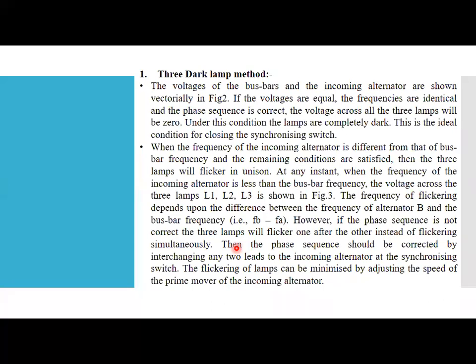And suppose we want to increase the frequency. So what do we have to do? We have to adjust the speed of the prime mover. If you want to increase the frequency, the prime mover speed will be increased. And if you want to decrease the frequency, the speed of the prime mover will be decreased. So first case, frequency is not the same. And once the frequency is matched, we can close the synchronizing switch.